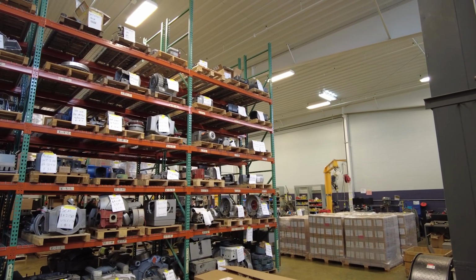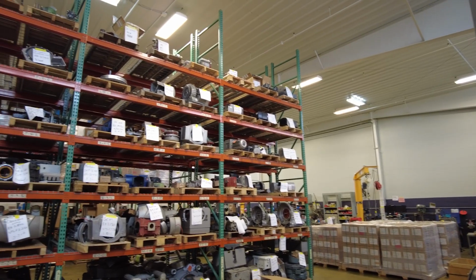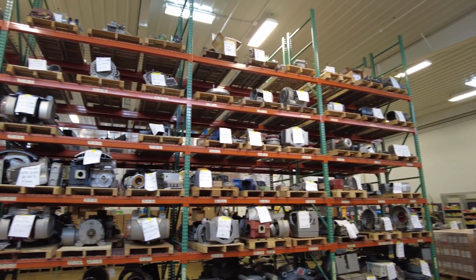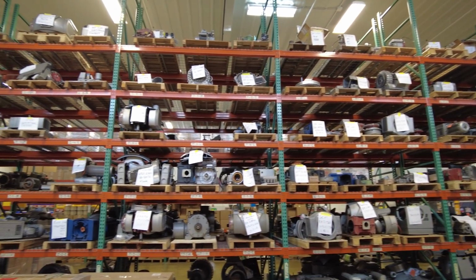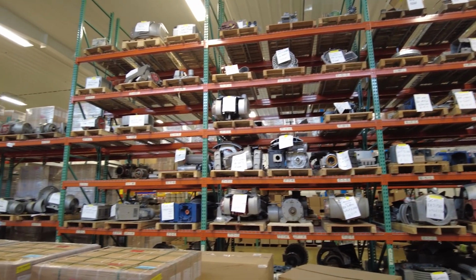So what that means is most of our motors in the US that we use are rated for 208, 230 volt, a low voltage, and 460 volt high voltage. Inside our motors is a terminal block. It's like a little plastic block with screws and metal plates we call jumper bars. All of the wires from the motor connect to that, and then the customer connects their power wires to that as well. Generally, there are two different configurations of those jumper bars that need to be moved around in position depending on whether they're running low voltage, 230 volt three-phase, or high voltage like 460 volt three-phase power.